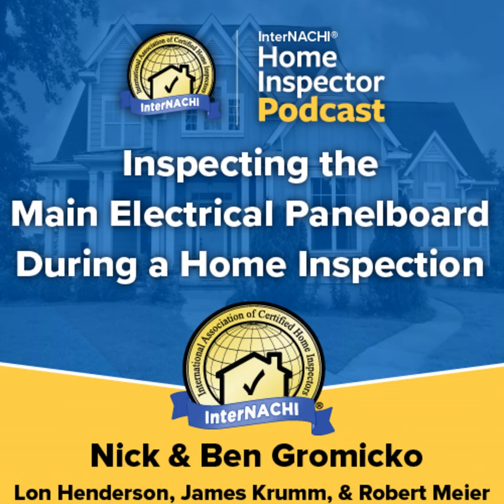Another example of an unprotected panel board could be when the bus bars might be coated with paint while the walls were being spray painted. There should not be any paint or wall texture sprayed on the wiring, connections, and buses inside an electrical panel. The general interpretation is that any contaminant that cannot be removed with a dry cloth is not allowed.